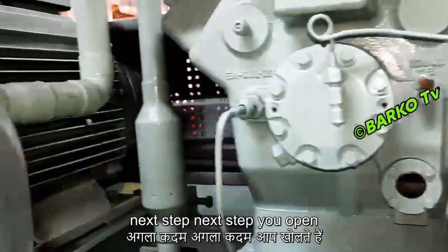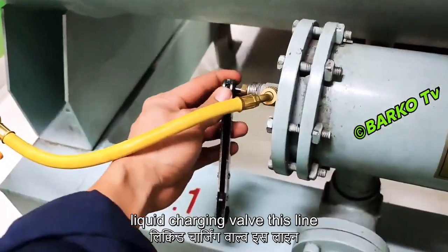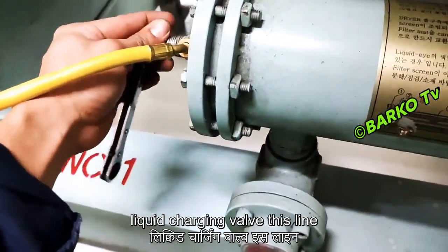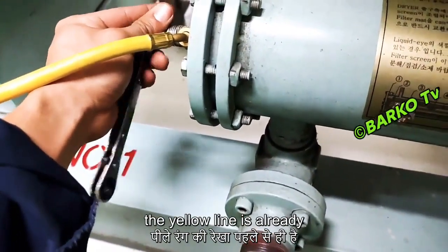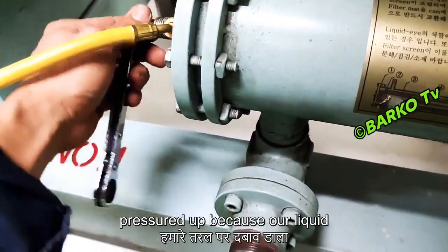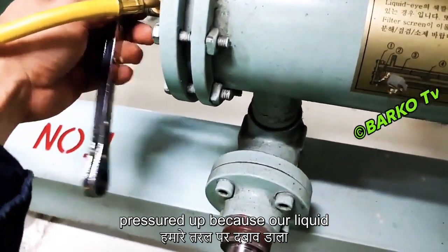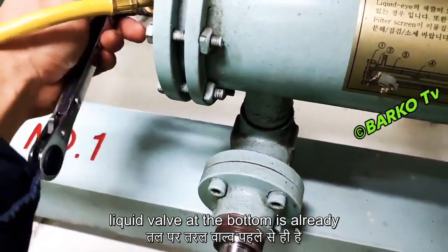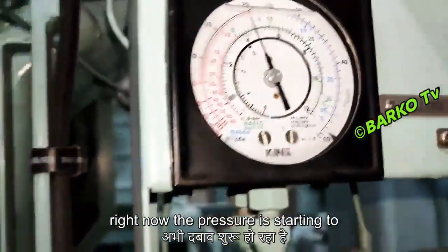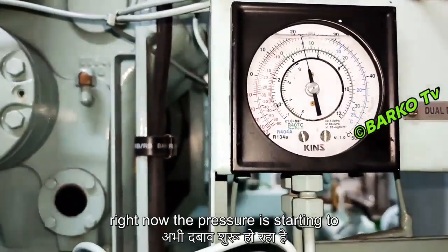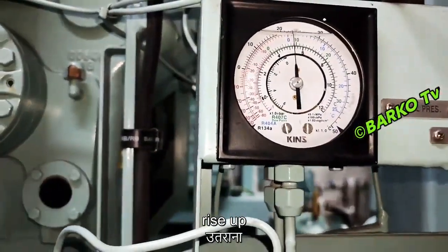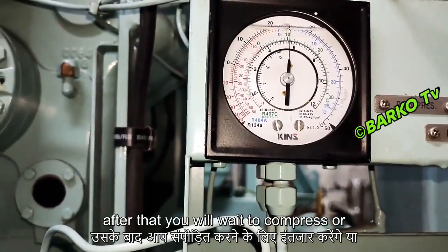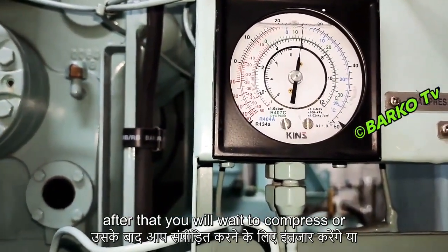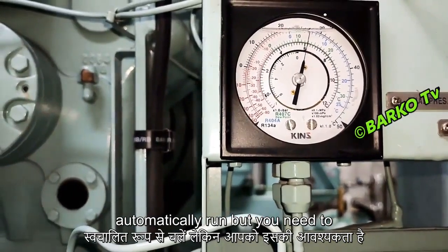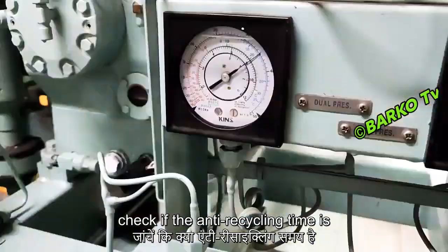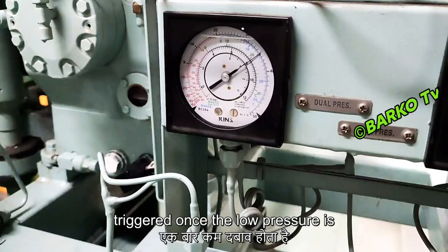Next step, you open liquid charging valve. This line, the yellow line, is already pressured up because our liquid valve at the bottom is already open. Right now the pressure is starting to rise up. After that, you will wait for the compressor to automatically run, but you need to check if the anti-recycling time is triggered.